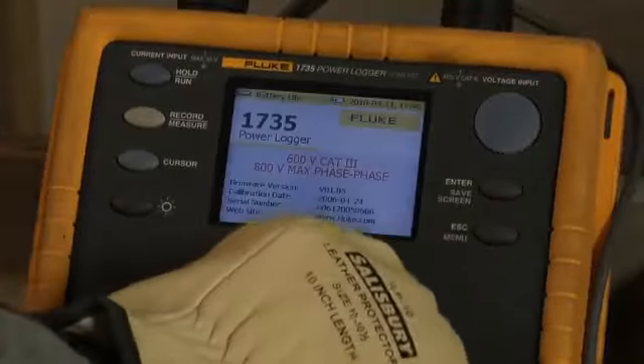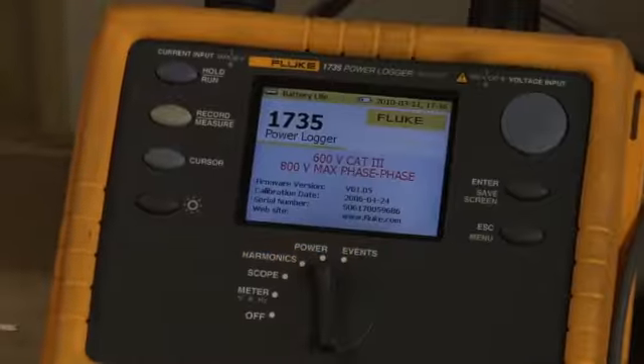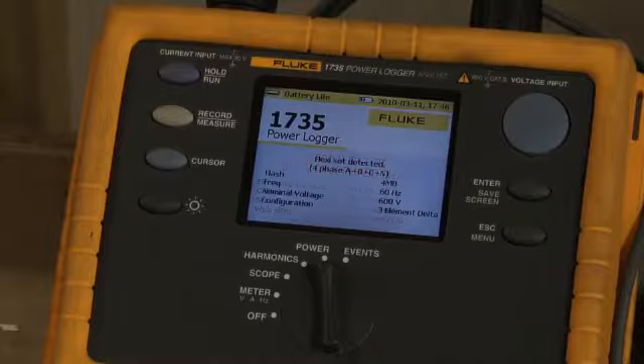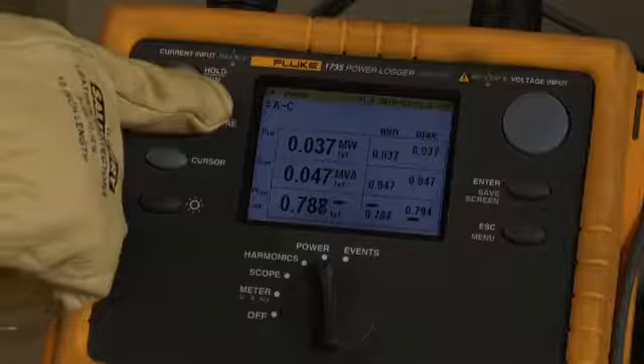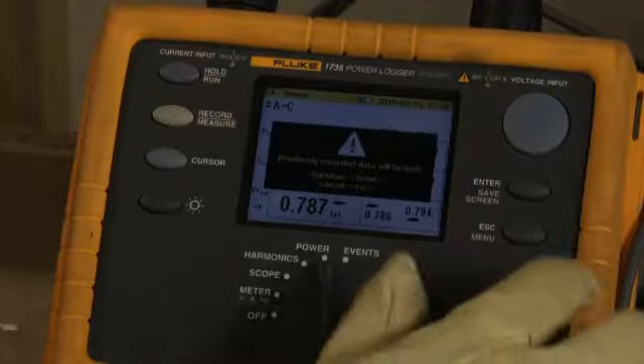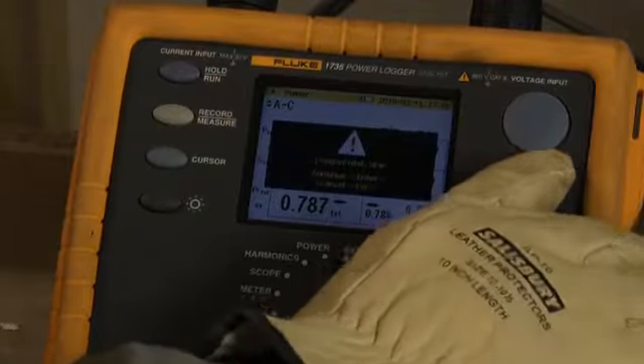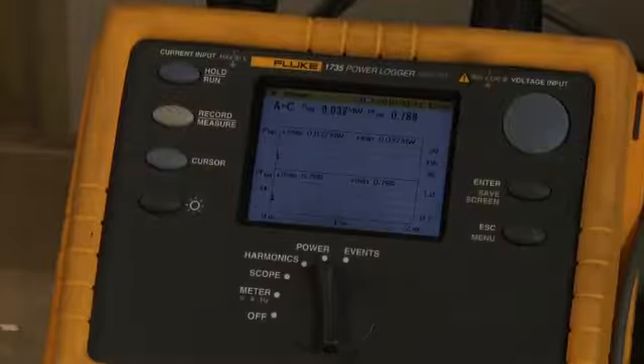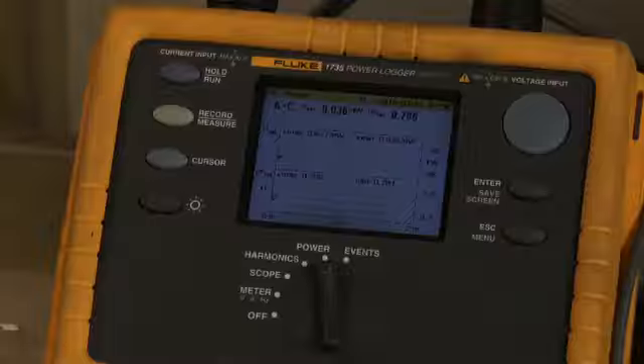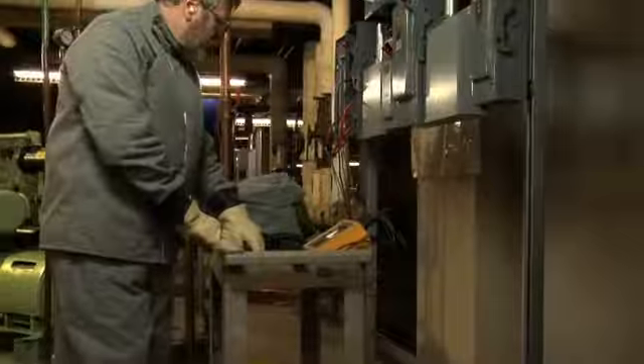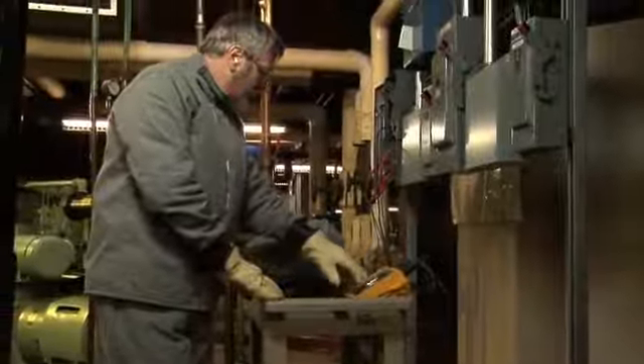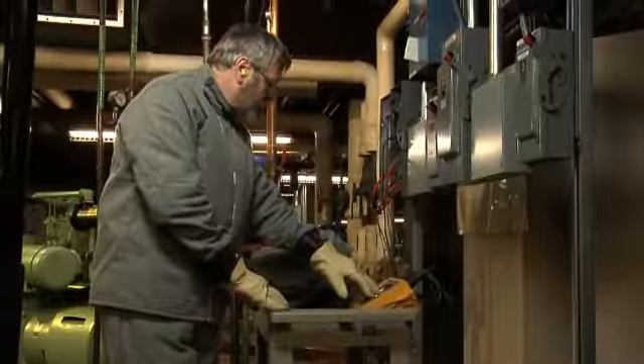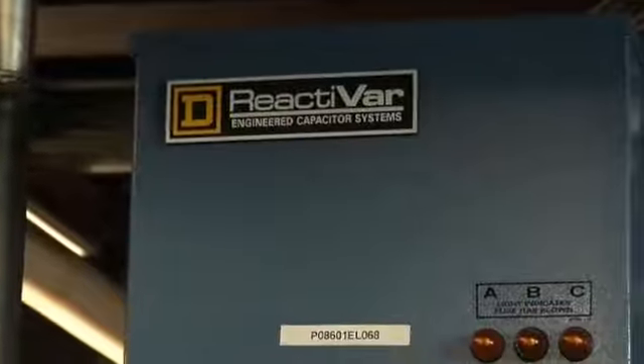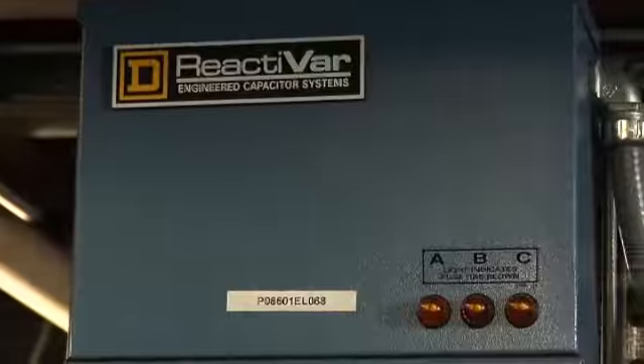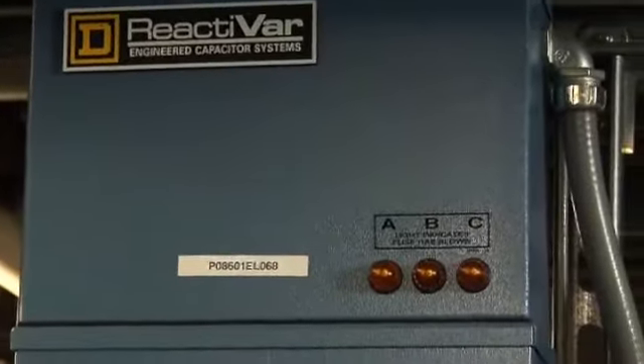On the power logger, turn the dial to Power to begin the process of recording data. Press the Record Measure button to begin recording. Press Enter to accept the information on the warning screens. You can now observe data being recorded on your power logger. Once you identify the problem load, use the data you logged to support corrective action, such as sizing a capacitor. It's better to install a small capacitor at the load than a large one at the service entrance.